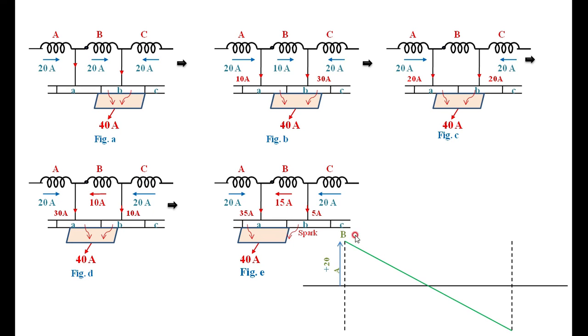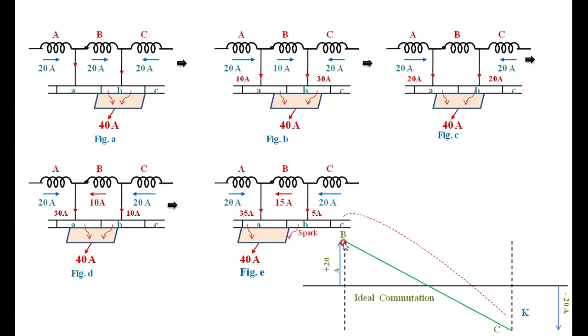The same thing is explained here: if it is changing from plus 20 amperes to minus 20 amperes, then it is called as ideal commutation. The reversal of current is taking place during the commutation period - the time taken from plus 20 amperes to minus 20 amperes is called the commutation period. If the current varies at a uniform rate from B to C in a straight line, then it is referred to as ideal commutation. However, due to the production of self-induced EMF in the coil, the variation follows a dotted curve because of the self-induced EMF opposing the change of current.